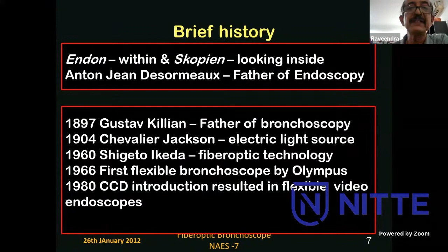So is there any difference between these two? Yes, they say the difference is, number one, the length of the insertion cord, which may be about 5 centimeters less than the bronchoscope. Then the number of working channels, the channels which enable you to pass an instrument. And flexible video endoscope is where there's a video at the end. Instead of optic fibers directly transmitting the image from the tip, it is the video camera which catches the image, which is then transmitted to the proximal part or the monitor, and it is flexible. That's called a flexible video endoscope.